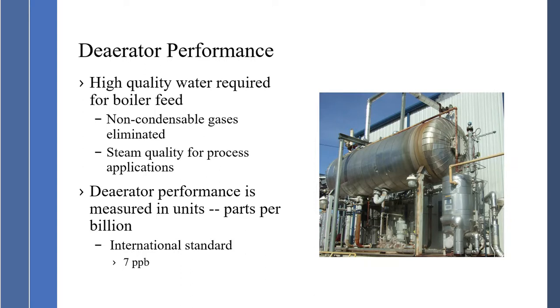Deaerator performance requires high quality water for boiler feed, with non-condensable gases eliminated. Non-condensable gases going with the steam into the process will suppress the temperature of steam — this is called partial pressures. Deaerator performance is measured in units of parts per billion. The international standard is seven parts per billion.